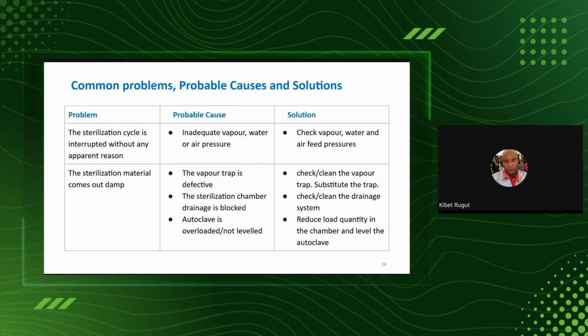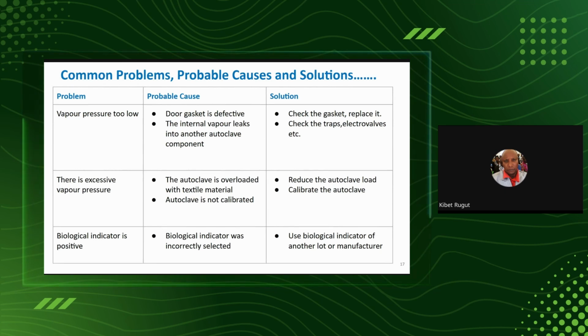So check the trap, and if you are not able to clean it, then substitute it. If you have a drainage system with blow down sections, then check on that again. Reduce the load quantity in the chamber and level the autoclave. It is very important to know that if there are no spaces between the packs, the steam penetration is compromised.